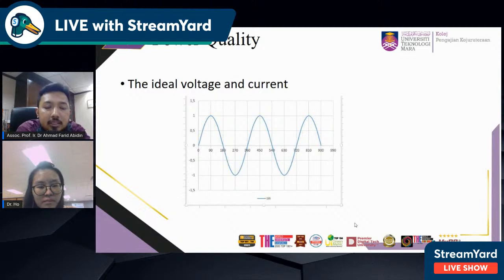As I mentioned, we need a very good sinusoidal shape, and in terms of magnitude we talk about per unit. Why? Because the voltage in our system varies depending on the area where we attach or install our equipment. For instance, at the transmission line the voltage should be 132, or can reach 500 kV, or it can also be 275. We cannot put a very specific voltage here because different parts will have different voltages, so to standardize the performance of voltage or current, especially voltage, we need to use per unit.